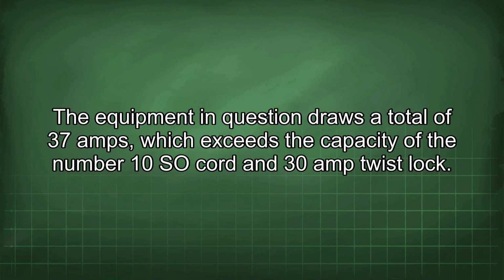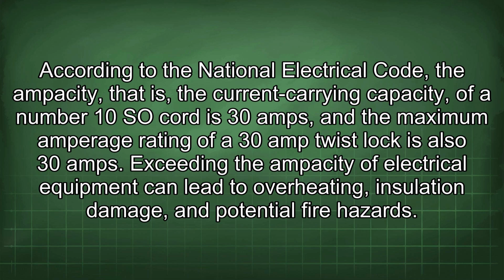The equipment in question draws a total of 37 amps, which exceeds the capacity of the number 10 SOW cord and 30 amp twist lock. According to the National Electrical Code, the ampacity, that is the current carrying capacity of a number 10 SOW cord, is 30 amps, and the maximum amperage rating of a 30 amp twist lock is also 30 amps. Exceeding the ampacity of electrical equipment can lead to overheating, insulation damage, and potential fire hazards.